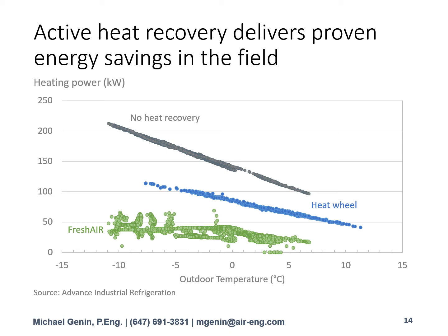If we start with the gray line, no heat recovery, this is where the existing unit was recorded with the heat wheel deactivated. And you can see it's essentially a perfect linear correlation, which we would expect given the amount of heat needed to be added to an airstream is proportional to the delta T. If we move down to the blue line, this is with the existing heat wheel unit. You can see that the line is not perfectly linear. The efficiency of a heat wheel is not going to be exactly consistent over the full operating range, but we have a substantial reduction in energy of about 40%.